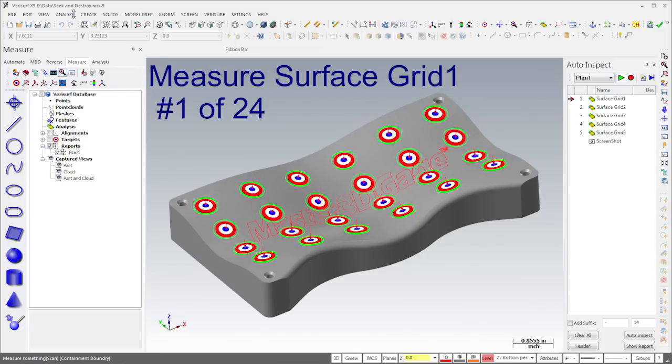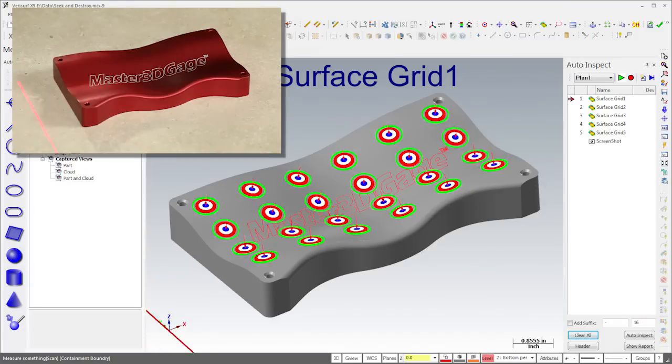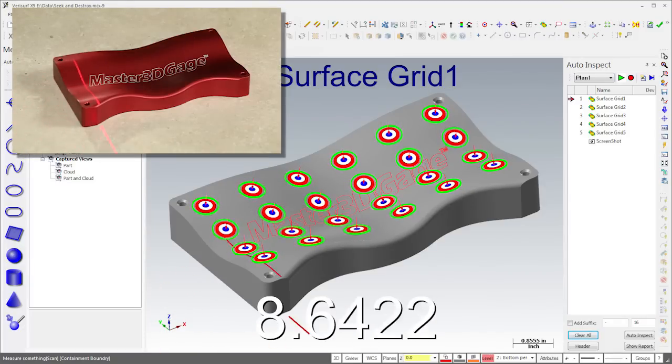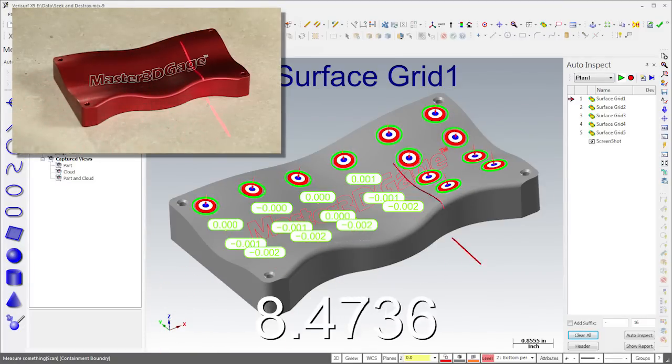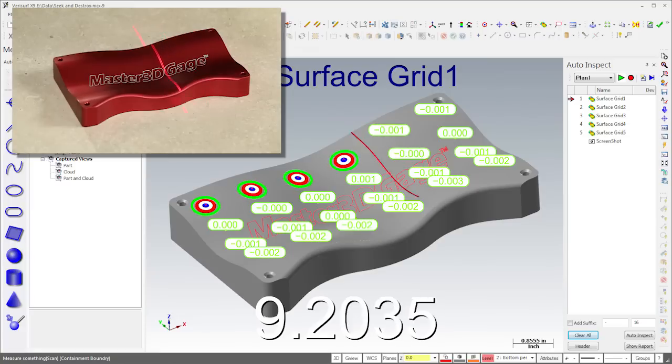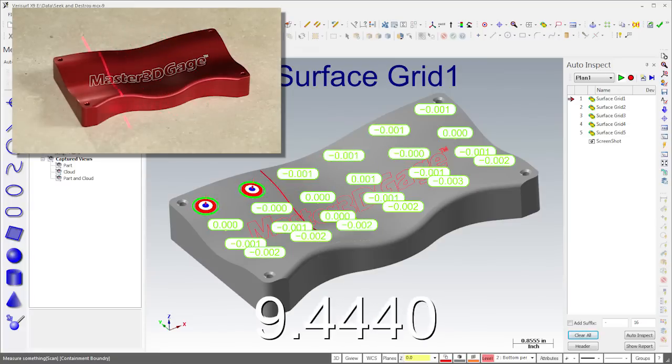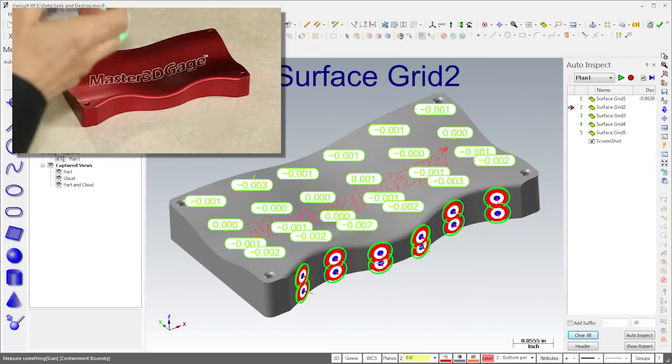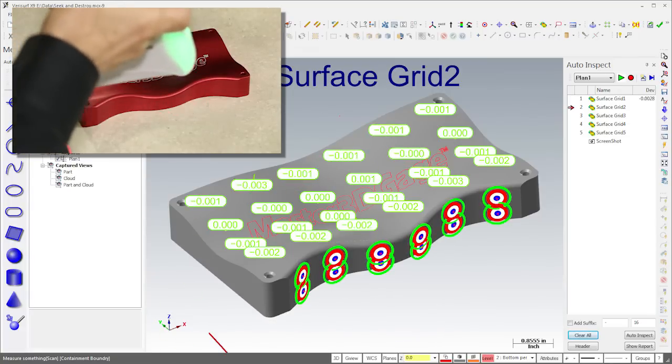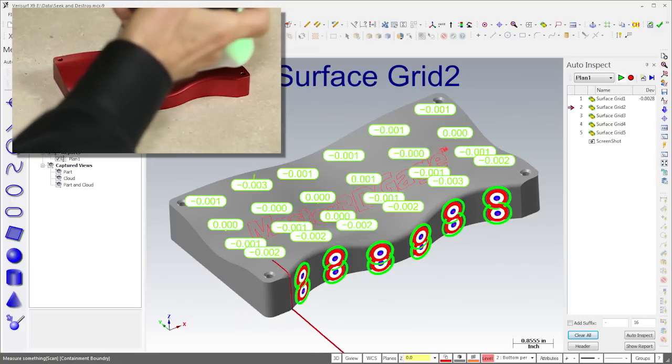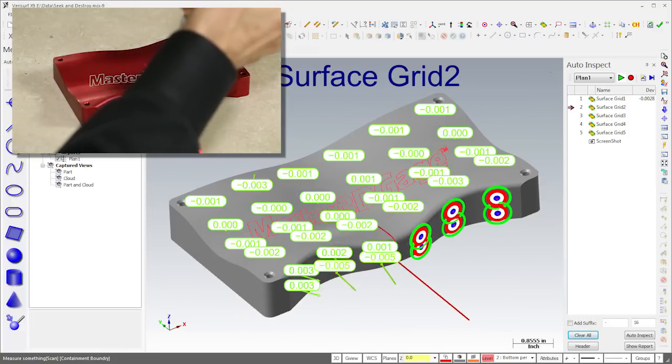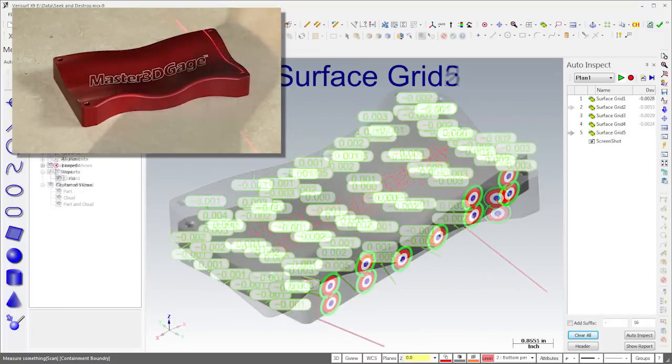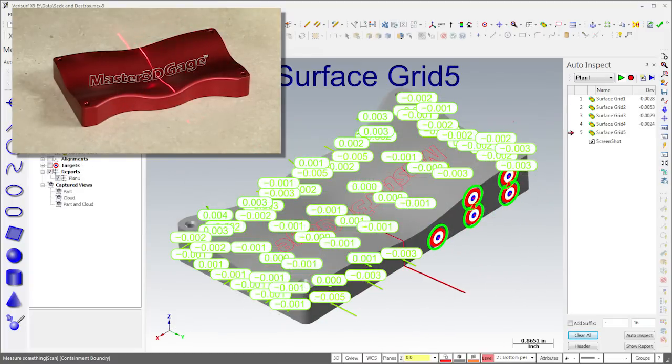When I do, VeriSurf highlights the targets in the first grid. To measure the targets, I simply sweep the laser across the part. VeriSurf averages the values in each target zone and displays the deviation. I'll complete the inspection by measuring the targets as each grid is highlighted. Notice that the plan automatically displays the best view for each grid.